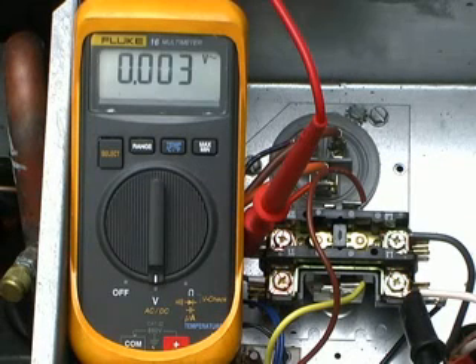So when I move the probe on the right, the top end of the screen, across the contact piece, we're reading 0 voltage. So obviously the voltage is not getting through the contact. So the contacts are burned, or there's ants in it, or trash in it, something. It's the only thing it can be in a case like this.